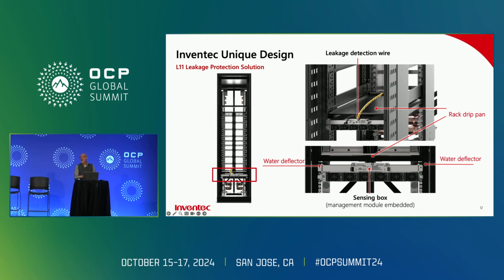This design channels any leakage into the bottom of the rack, into the drip pan, and it's there that we sense the leaks and are able to trigger warnings that go back to the rack level management system.